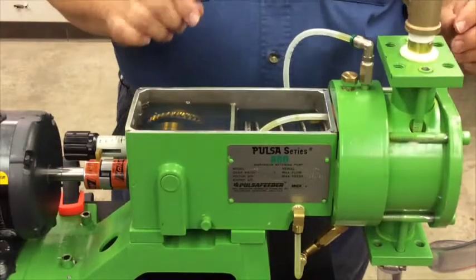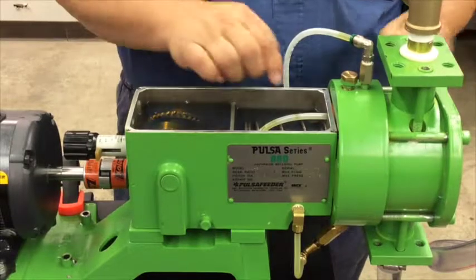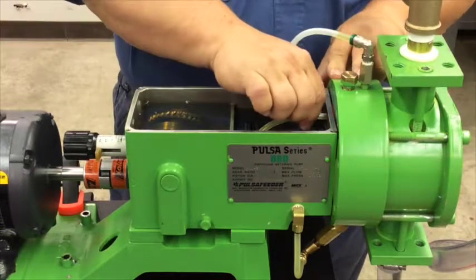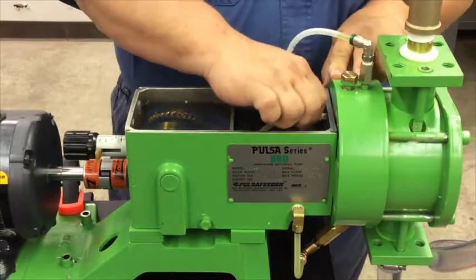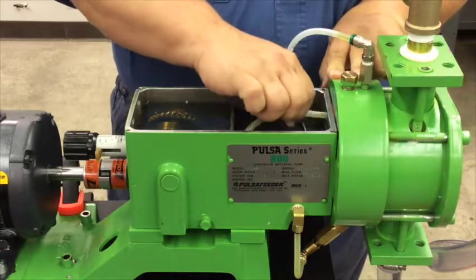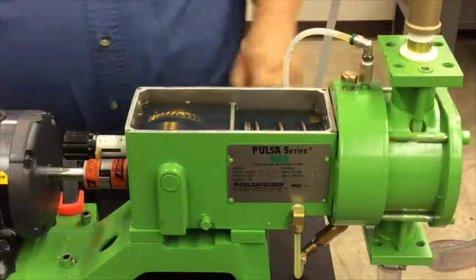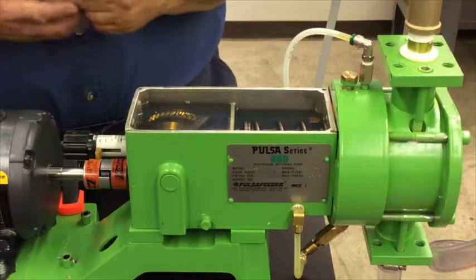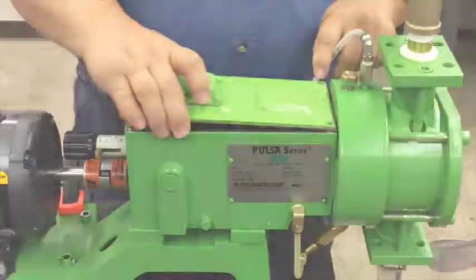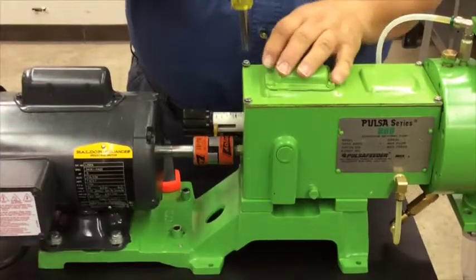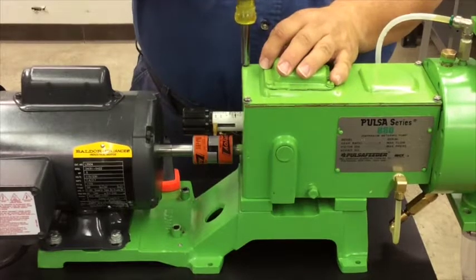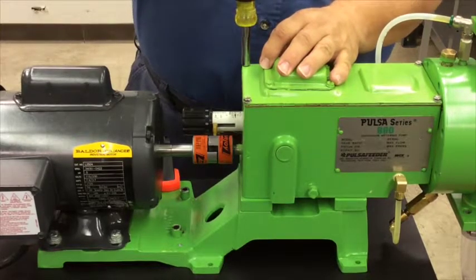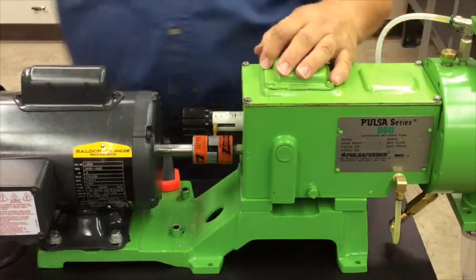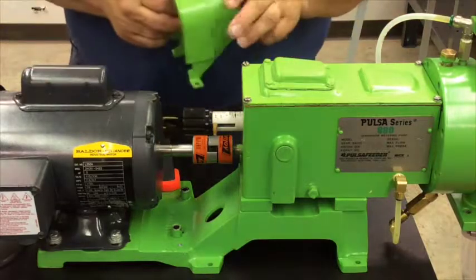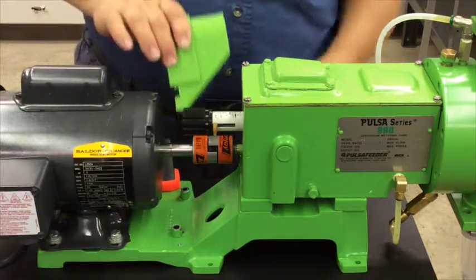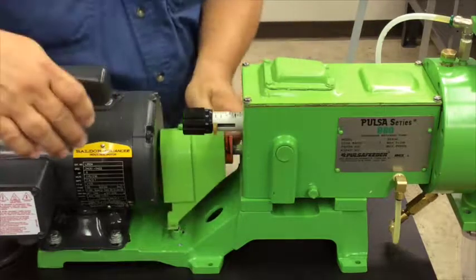I've completed the adjustment of the hydraulic bypass screw, and now what I'm going to do is remove my tube here that we used to perform the test or the procedure. And the next thing I'm going to do is replace the cover. Okay, got that cover almost on. I'm just going to tighten down the last screw. Perfect. The next thing I'm going to do is replace the coupling guard.